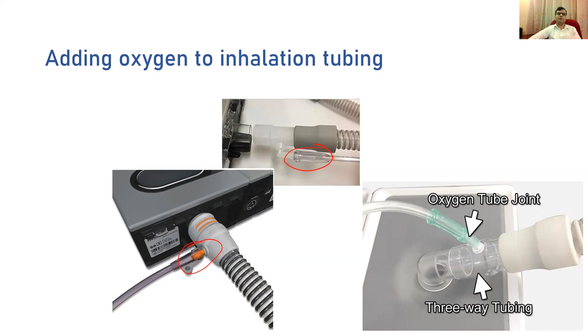So this is how the oxygen is added into the device. The problem with this attachment is that it affects triggering. Flow is quite important to trigger the device when the patient is breathing in and out. But when you add oxygen outside the device into the tubing, the device has no understanding of how much flow you are adding.